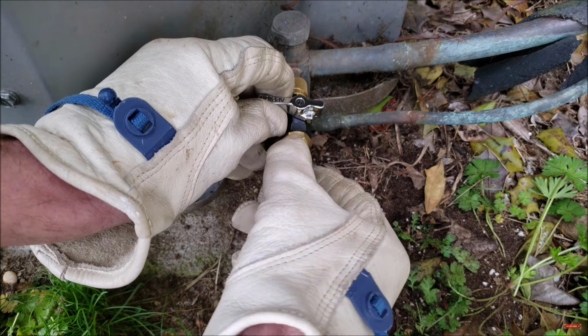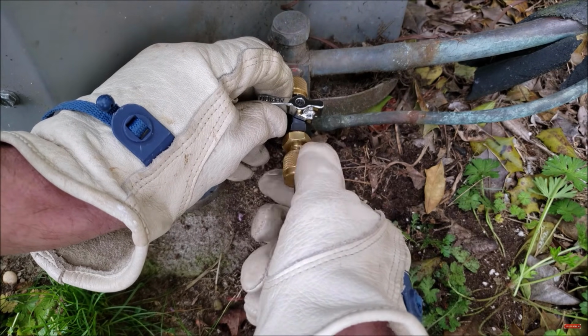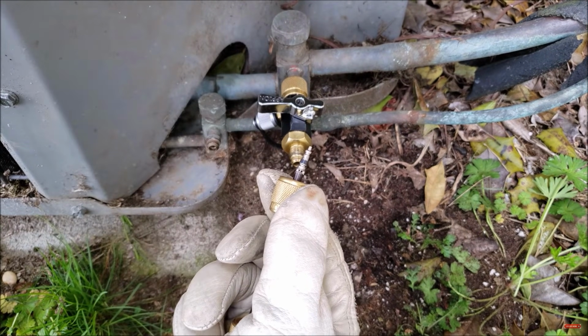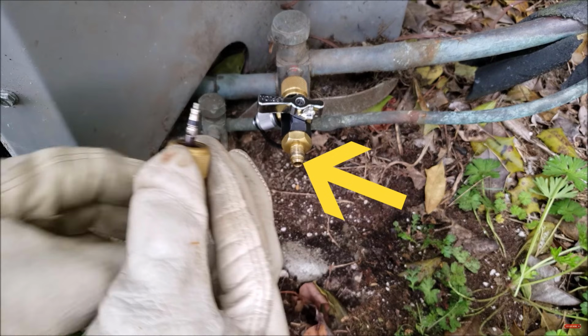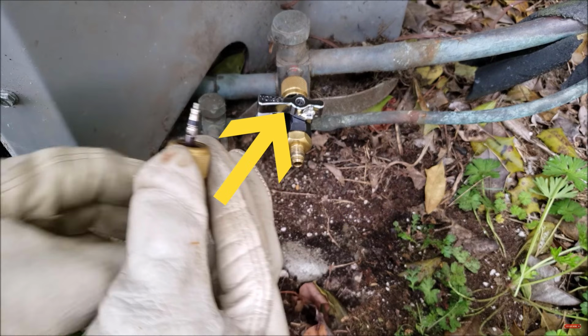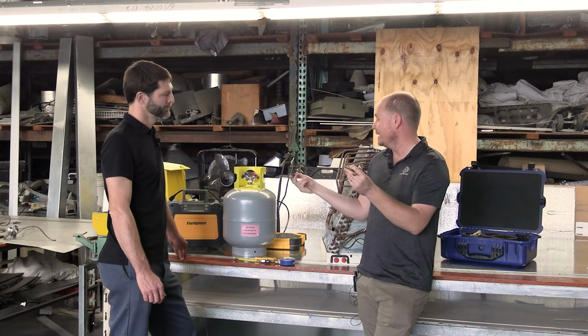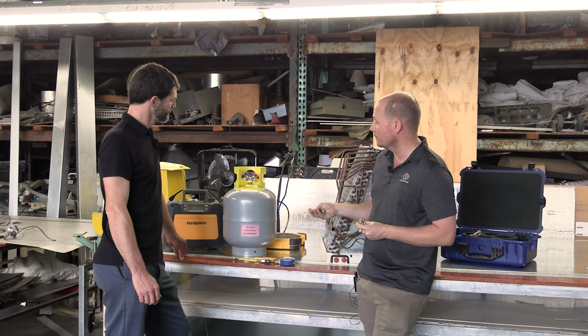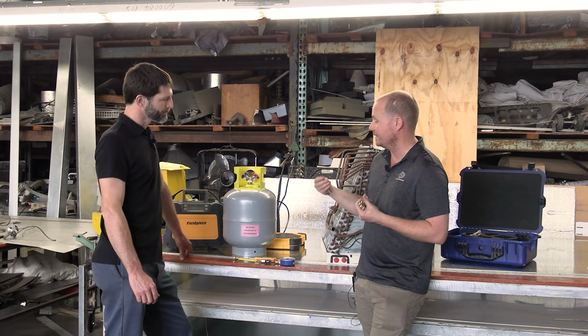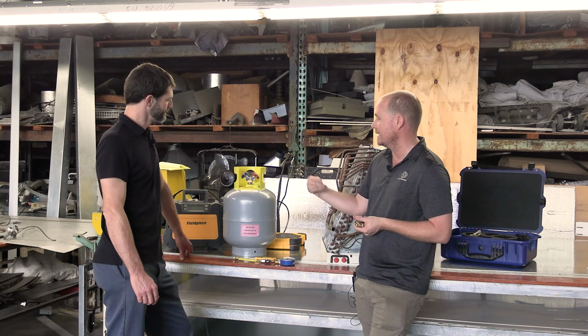This is where you're going to connect for recovery. This is where you're going to connect for your vacuum with this in place with the core out. And now you also have that added benefit of having that control in place. So very simple. Pull those out. It's going to reduce the amount of impedance to the refrigerant flow. It's going to make it go quicker.